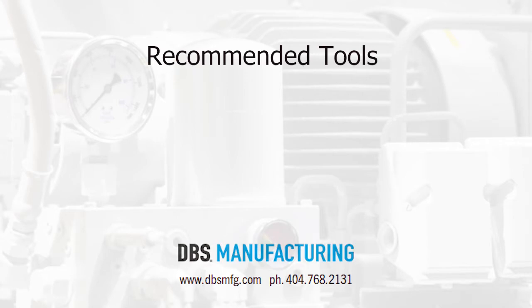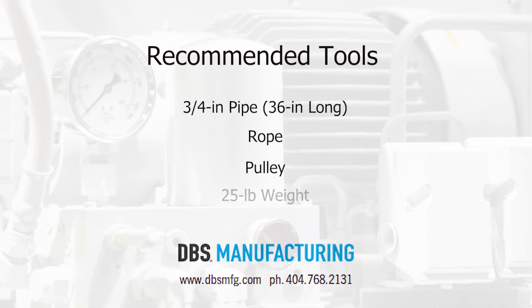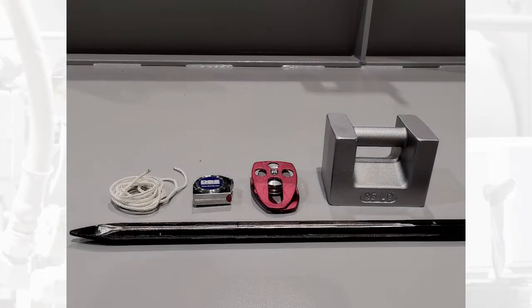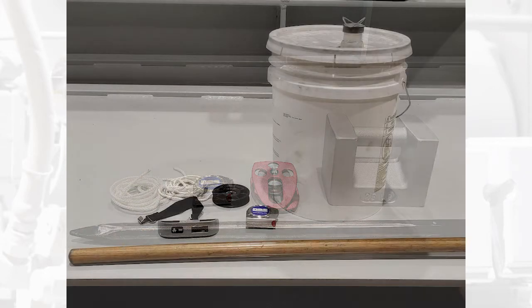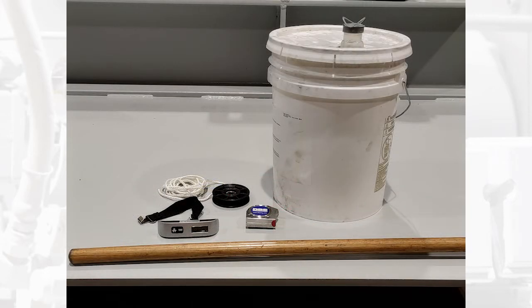For this procedure, you will need a 3/4 inch pipe of at least 36 inch length, a rope of at least 25 pound pull strength, a pulley, and a 25 pound weight. If you do not have one or more of these materials, you may be able to improvise. For example, a breaker bar or sturdy broomstick can replace the 3/4 inch pipe. You will also need a second person available to help with the calibration process.